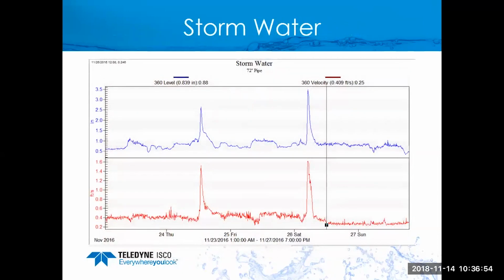And here's some of the data from that site. So you'll see they had a couple storm events. Everything picked up fine. But when they did not have a storm, on the line that I have indicated there, the level was 0.88, so less than an inch deep, and it was 0.25 feet per second. So incredibly slow velocity, a challenging location at best.